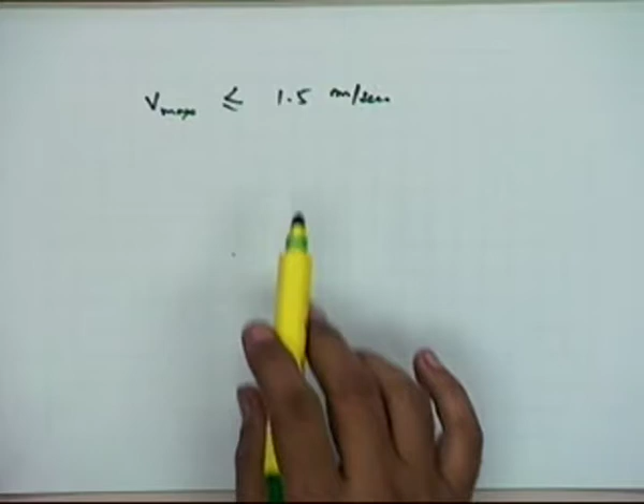So the maximum velocity in the pipe, this is the restriction enforced, especially in those cases where the bends are there, where you might have problems of eddy formations, especially in the case of lateral. You have 2 places where there will be just a sudden change of direction of the flow. One will be when the water is coming from the main line and entering the lateral. The other place is when the water is coming from the lateral and entering the riser pipe, and then coming to the sprinkler head. So from that criteria, to avoid those situations where you have the excessive loss, you try to restrict the maximum velocities to be less than this value. There is also another additional parameter which has to be looked into.